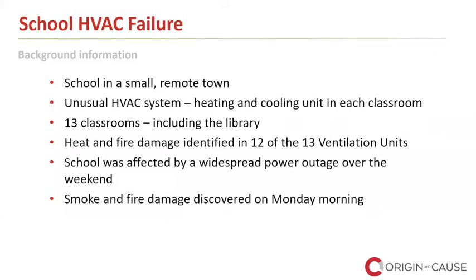There was a distributed heating and cooling unit, an independent heating and cooling unit in each classroom. There were 13 classrooms in the building, including the library. Heat and fire damage were identified in 12 of the 13 ventilation units. The school was affected by a widespread power outage over the weekend, and smoke and fire damage was discovered Monday morning when staff first arrived for the school day.